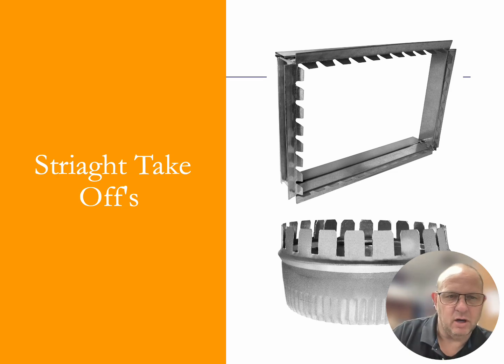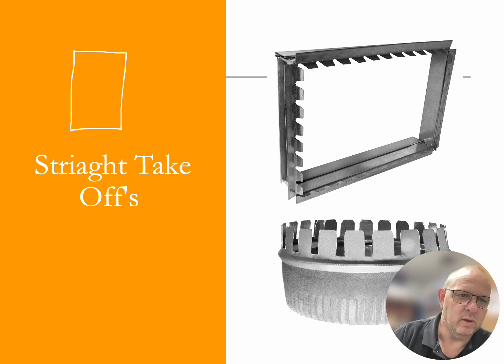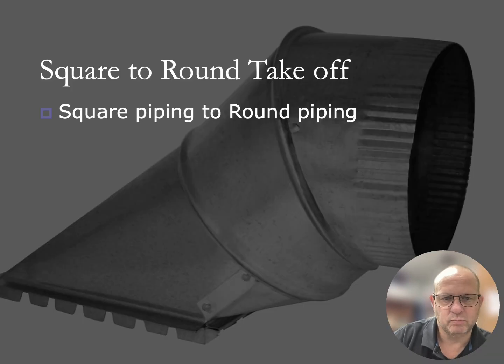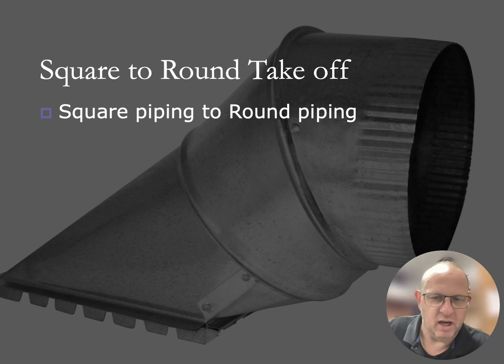So the takeoffs are what's going to come off of the plenum and move that air from the plenum into our boots, and we'll talk about those in a little bit. Now, takeoffs come in a variety of different applications. We can have the transition takeoffs where we are transitioning from one size to another, and that would be a square duct. And in my next slide, I'll show you that transition takeoff and the plenum on an actual installation that we have done.